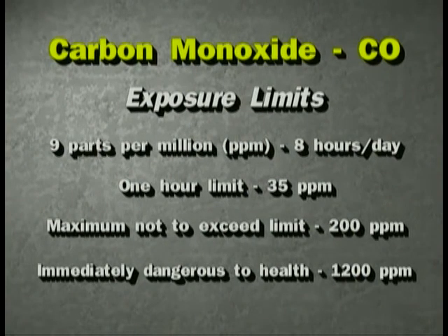Indoor exposure limits set by professional and government agencies include 9 parts per million over 8 hours of the day, a 1-hour limit of 35 parts per million, a maximum not to exceed limit of 200 parts per million, and an immediately dangerous to health limit of 1,200 parts per million.